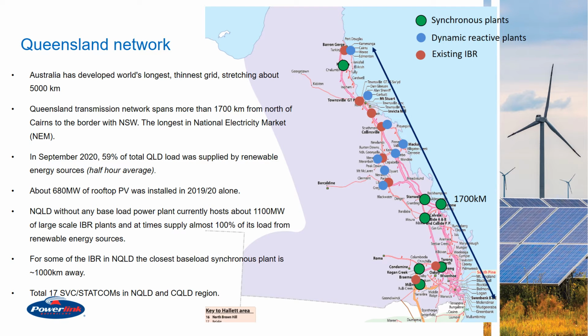This is a map of Queensland transmission network showing synchronous plants, existing IBRs and SVCs. Some interesting facts about Queensland transmission network make Queensland network very special not only in Australian context but on a global scale. Australia has developed world's longest and thinnest grid, stretching about 5,000 kilometers, and Queensland transmission network is the longest in NEM, spanning over 1,700 kilometers. In September 2020, 59% of the total Queensland load was supplied by renewable energy sources. About 680 megawatt of rooftop PV was installed in 2019-20 alone, which is very close to the biggest baseload generator in NEM, that is of 750 megawatt.